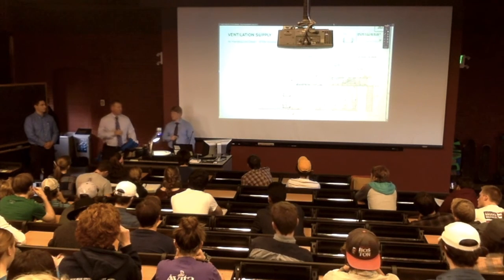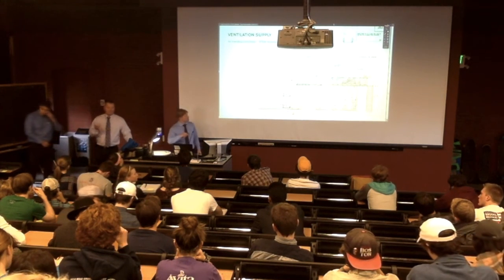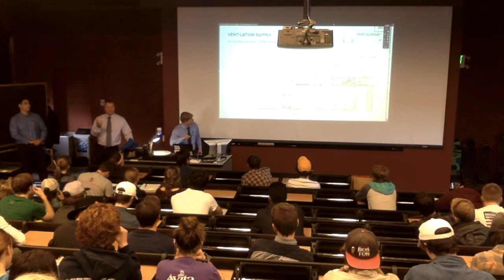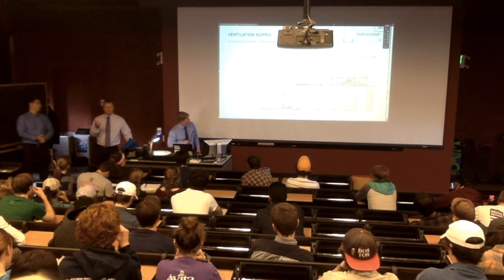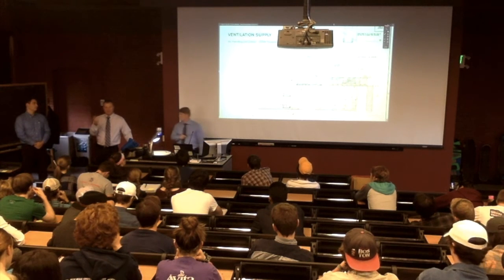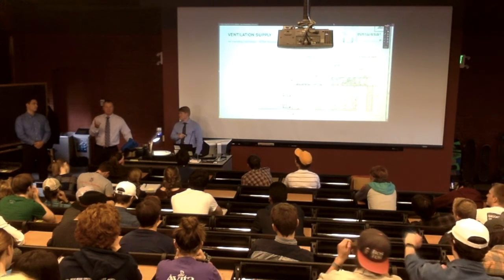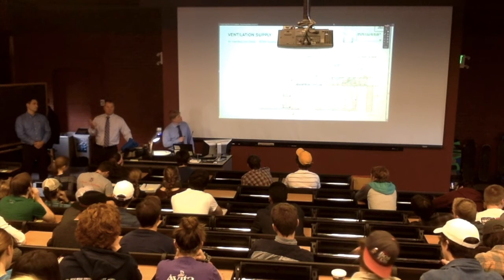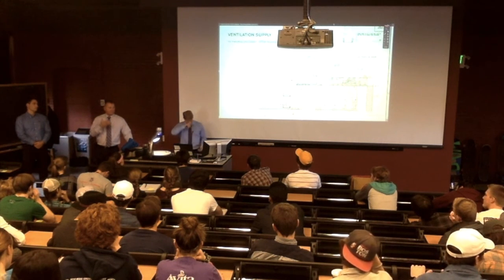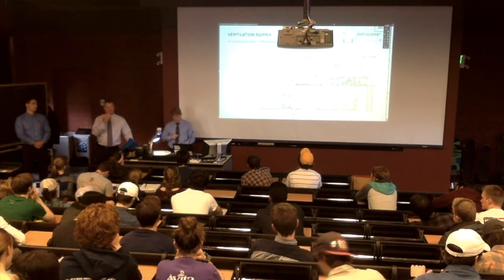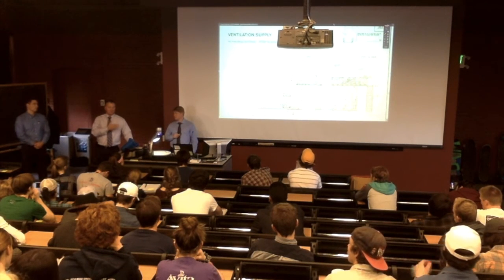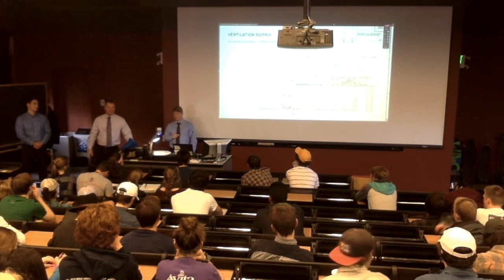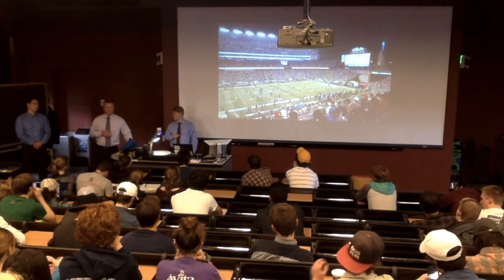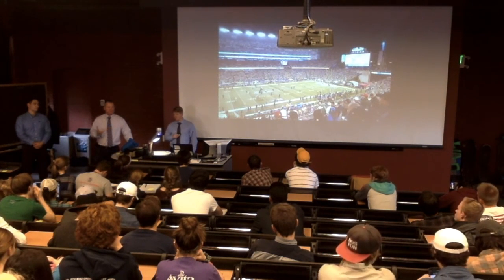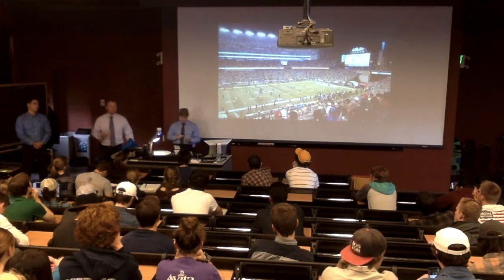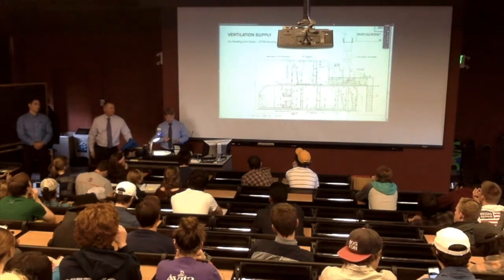But as an example, the motors have this L10 of 200,000. So that means that it's good for 200,000 hours. If you take 200,000 hours divided by 8760, you can understand that it's good for a long time. So we try to pick all the components in the equipment to make sure that they have a longer lifespan, but you still have to grease bearings, you still have to change filters, you still have to do a lot of different things in the equipment.